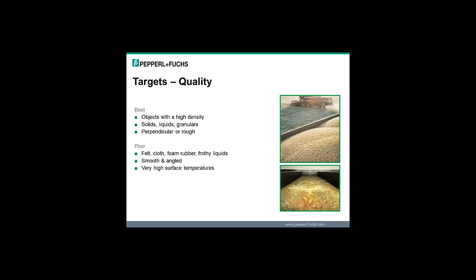Poor targets: felt, cloth, foam, rubber, frothy liquids, all of those absorb sound. So if you want a good reflective echo to come back, you want something that's going to reflect the sound very well, and soft targets, fluffy targets, cloth, things like that are not the best. It's not to say you can't detect them, but you've probably got to be quite a bit closer than you would something of a higher density. Smooth and angled targets I mentioned before, they can be detected, but again, you've either got to be a lot closer or you've got to make sure that you've got a perpendicular axis for your detection.